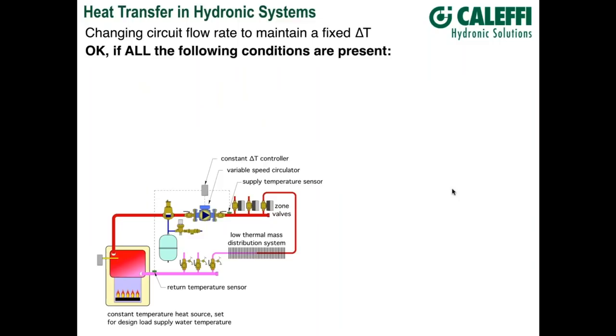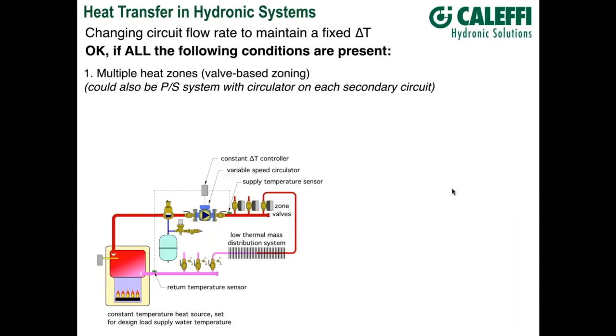What happens if we constrain our delta T — that is, have some control that holds delta T constant? This comes up often. It's acceptable and will work, but there are some constraints. First, you need a valve-based zoning system — that could be zone valves, thermostatic radiator valves, manifold valve actuators, or a primary-secondary system with a circulator on each secondary circuit. In other words, when a zone shuts off, we have less flow and less heat transfer. The second condition is low thermal mass.